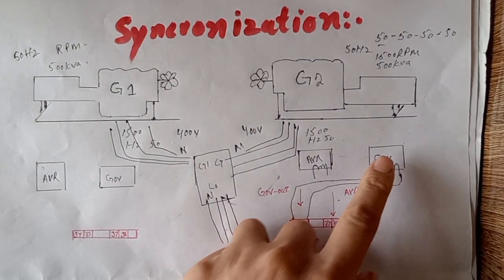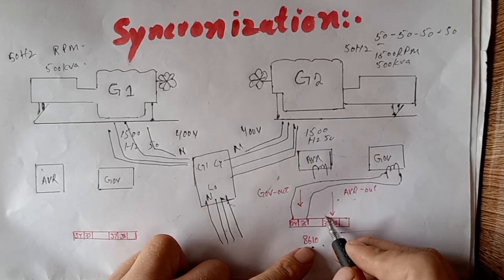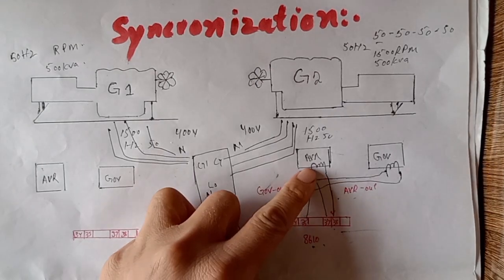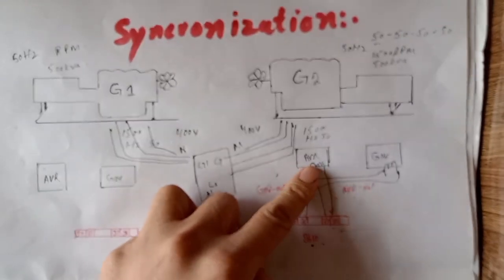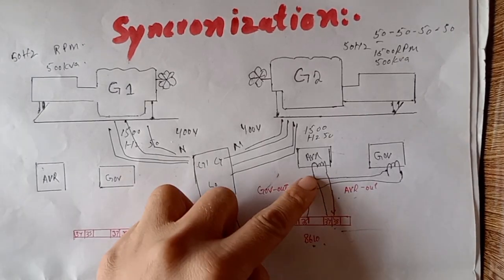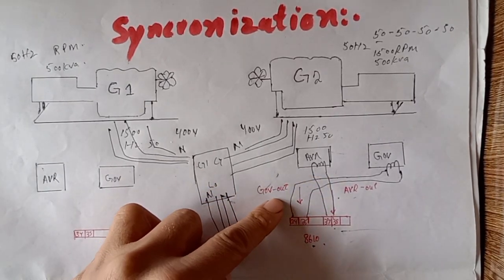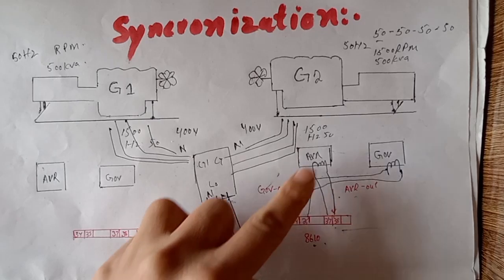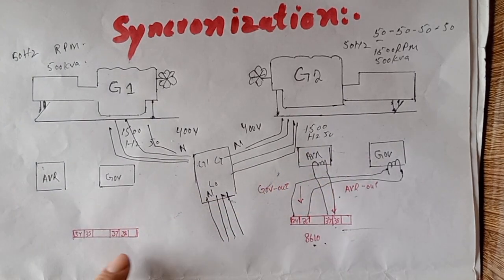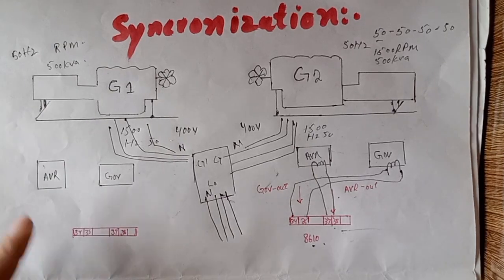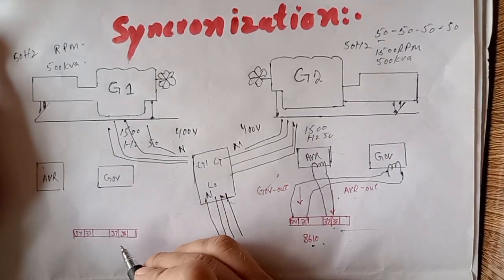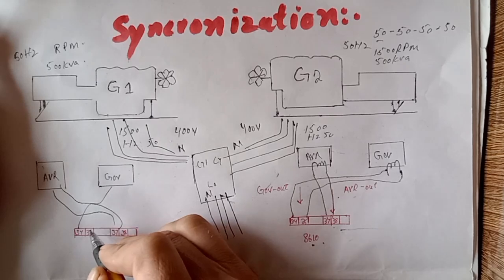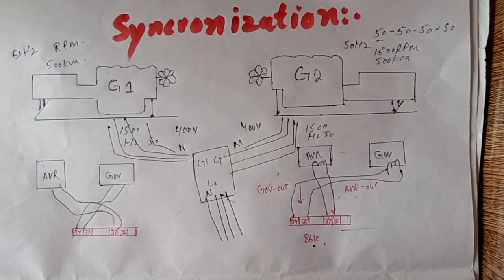The AVR also has remote control two terminals, and the DFC controller controls the AVR through the remote control potentiometer automatically. It applies 5 to 7 volts DC out of a maximum 10 volts DC to control the AVR and the governor. The same is done for the second generator — controlling both the AVR and the governor. Two wires go to the AVR and two wires go to the governor.